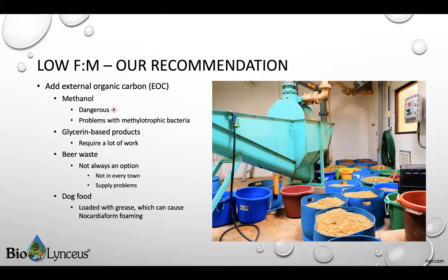Glycerin-based products are not the most efficient because they require a lot of product to accomplish the same goal as methanol and other external carbon sources. Beer waste is something that a lot of facilities are turning to these days. However, not every town has a brewery willing to sell or donate their waste. And some towns may not have a brewery at all. Not to mention, you would need a lot of beer waste, and only large breweries brew at the scale required to feed wastewater facilities.